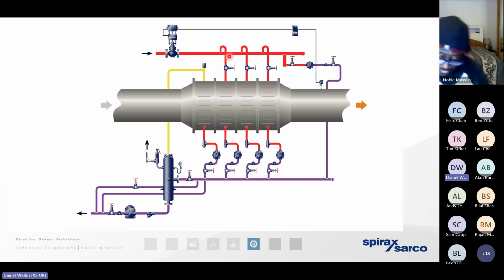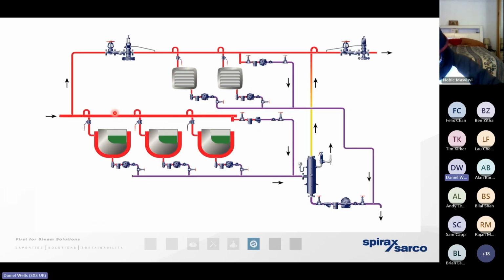For example, if we've got high pressure, high temperature condensate depressurizing across a failed trap, the flash steam that is collected by the flash vessel can be diverted back to a preheater in the same process, for example. That's what we call an in-step process. Or there may be applications where we can take the flash steam that is produced by one process, collect it in a flash vessel, and divert it to a completely different area of site, a different process.